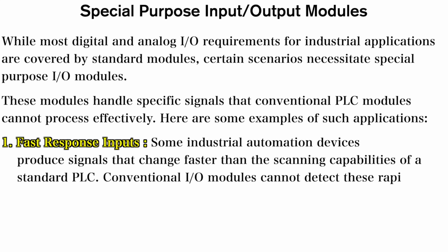First, fast response input. Some industrial automation devices produce signals that change so fast that the scanning capabilities of a standard programmable logic controller cannot match them. So the conventional input output modules cannot detect these rapid changes and cannot respond in a timely manner, and the operation cannot be effective. So in that application, fast response input, we use the special input output modules.